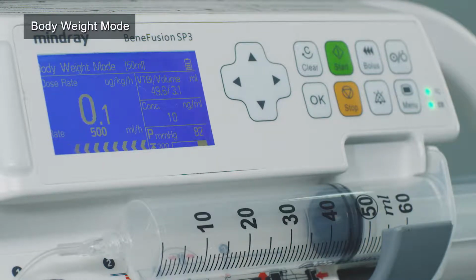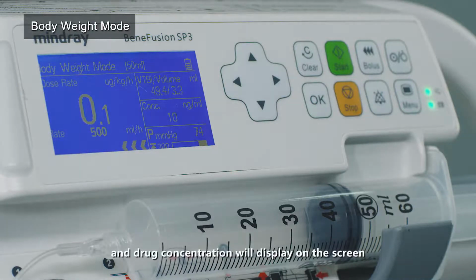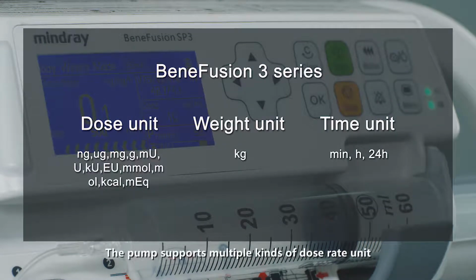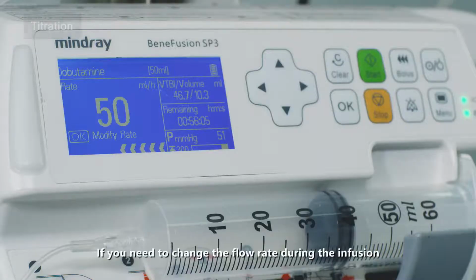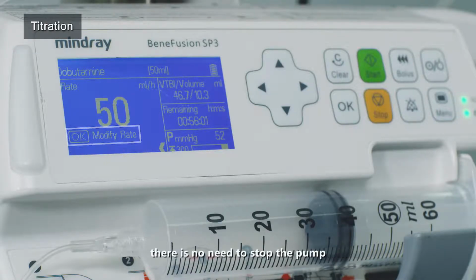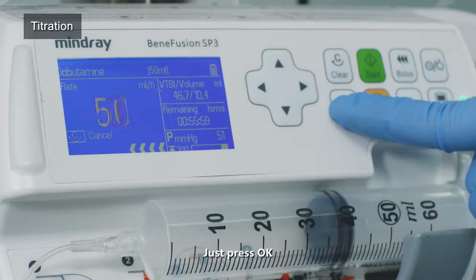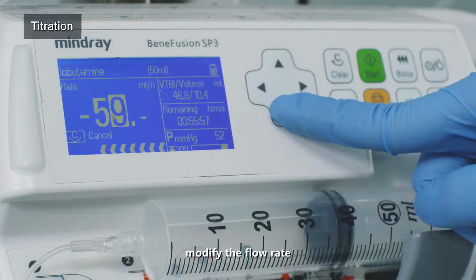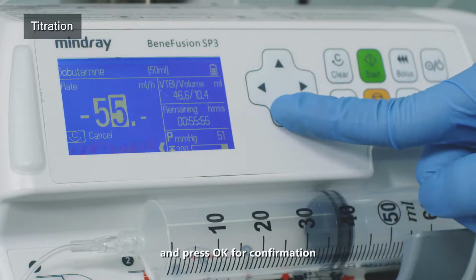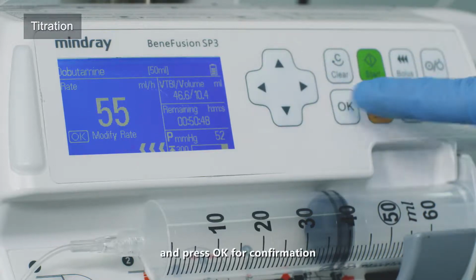The dose rate, flow rate, and drug concentration will display on the screen. The pump supports multiple kinds of dose rate units. If you need to change the flow rate during the infusion, there is no need to stop the pump. Just press OK, modify the flow rate, and press OK for confirmation.